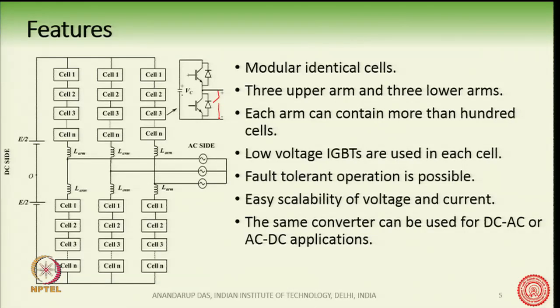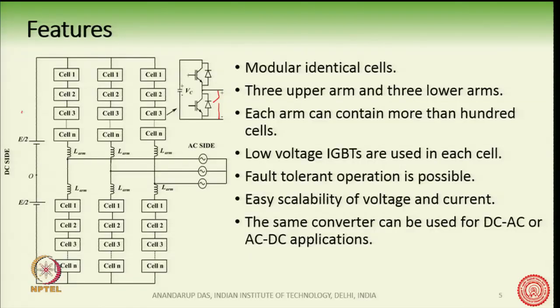Each cell has its own capacitor, two switches, and a bypass feature. An attractive feature of MMC is that low-voltage transistors or IGBTs — for example, 3.3 kV or 2.5 kV IGBTs — can be used in each cell. Since many cells are connected in series, we can reach very high voltages, such as ±400 kV on the DC side.